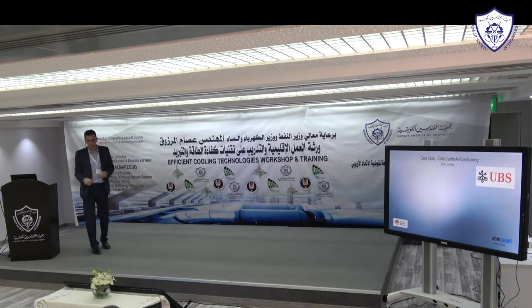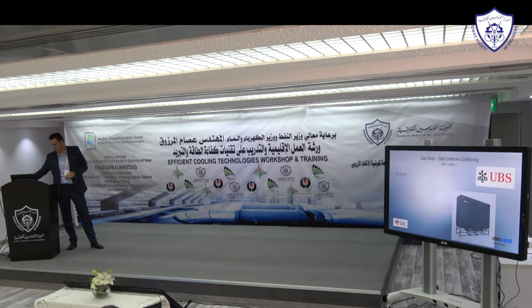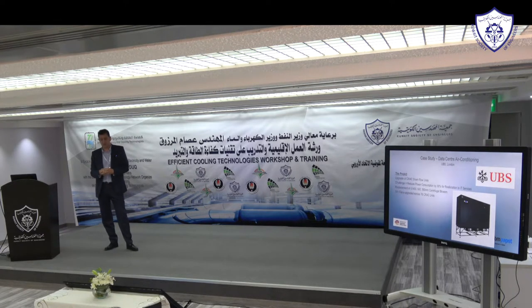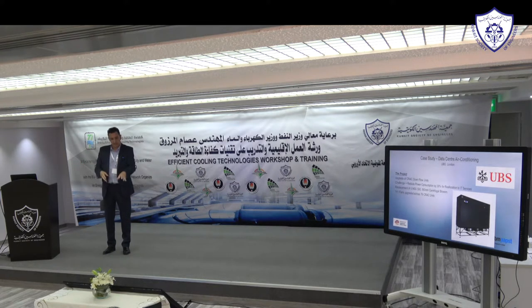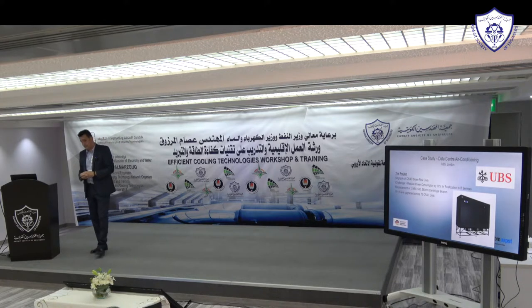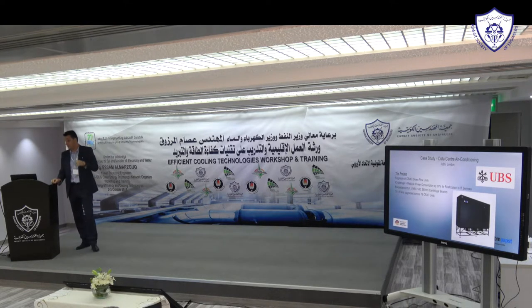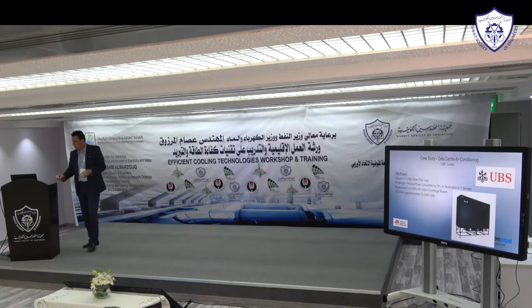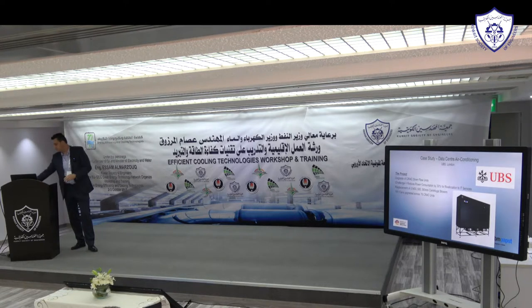The second opportunity: data centers. This is a relatively small data center in London — UBS Swiss bank. The project was to upgrade some close control air conditioning units — downflow units, where the black box sits on top of a raised floor, the fan section goes underneath, and blows air through the data center and up through the IT equipment. Air conditioning is a huge problem for data centers, and the challenge here was to reduce power consumption by 30%, freeing that electricity to power the IT equipment they're actually paid for. It involved replacement of centrifugal blowers — nearly 200 fans across 76 units in this 190,000 square foot data center in central London.